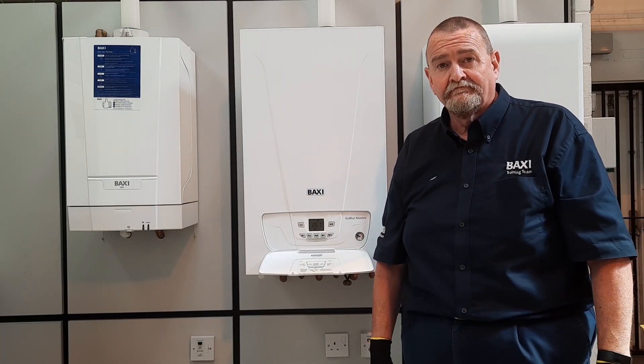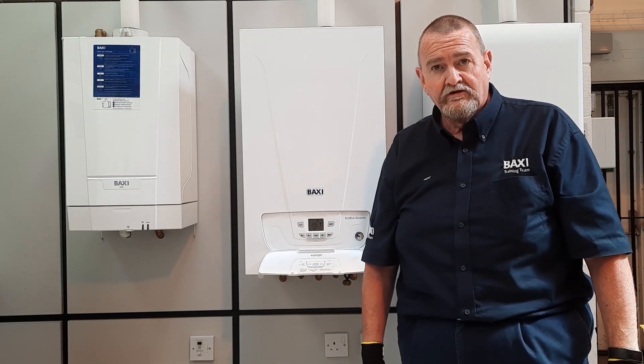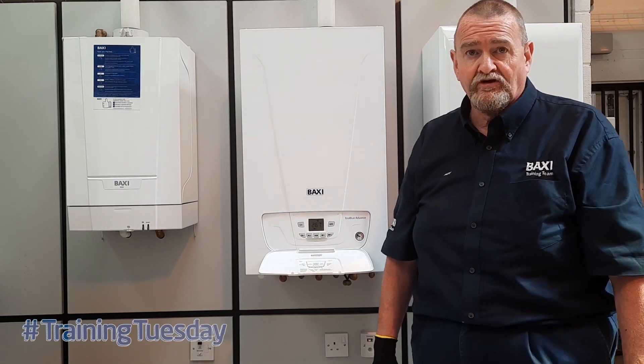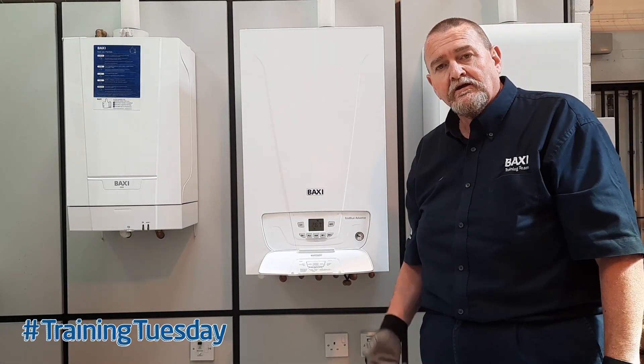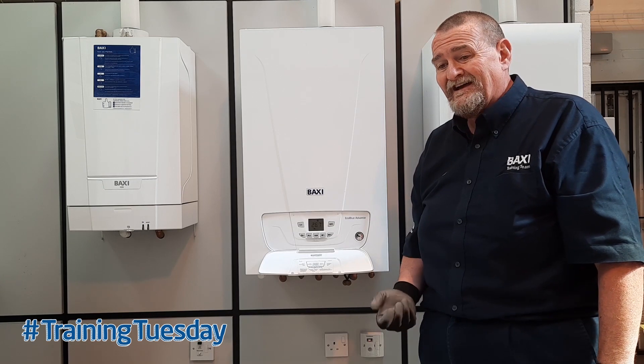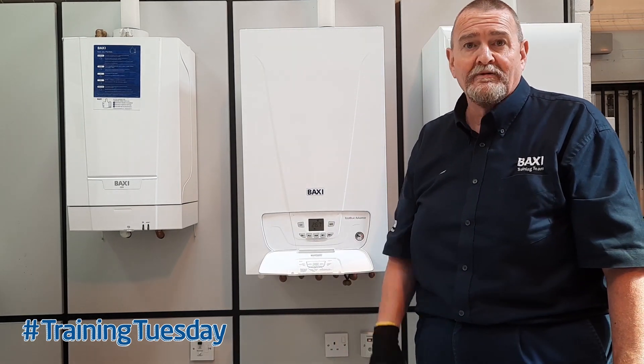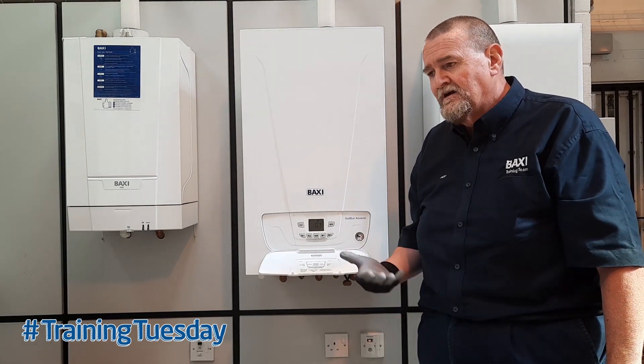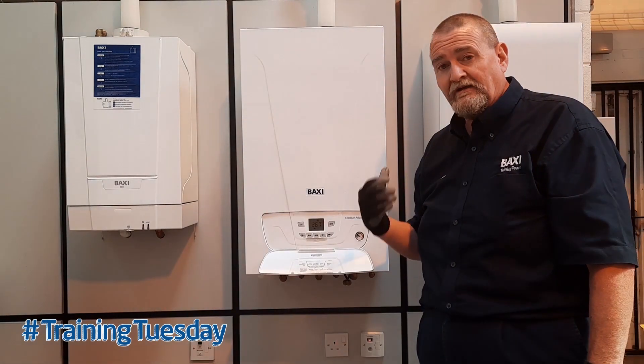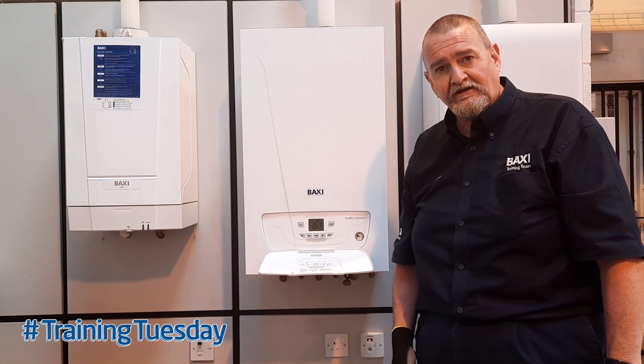Hi guys, it's Roy Fugler here again at the Baxi Training Centre in Warrington with another Baxi Training Tuesday top tip. We've been called out to this ECO Blue Advance — the customer's been complaining that they're topping the pressure up on a regular basis and that water's coming out the PRV, typically when the heating's on or when they're running a bath. My initial diagnosis would be that the expansion vessel has lost its charge, so we'll investigate that.